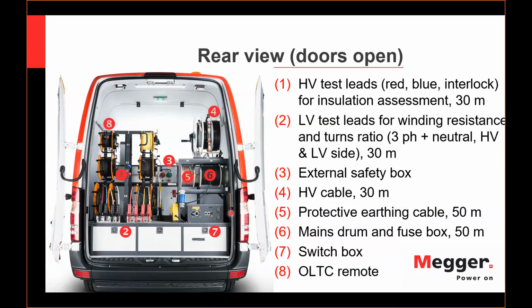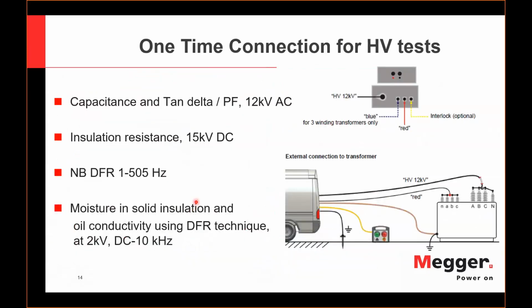The main piece of equipment here is the switch box, basically something that allows you to share the same cable connection that you established between the test object and your van, and interconnect this cable to different instruments on board. So the main idea is that we try to make a one-time connection for the HV tests and a one-time connection for the LV tests. You see here a van and a number of cables that go out of the van.